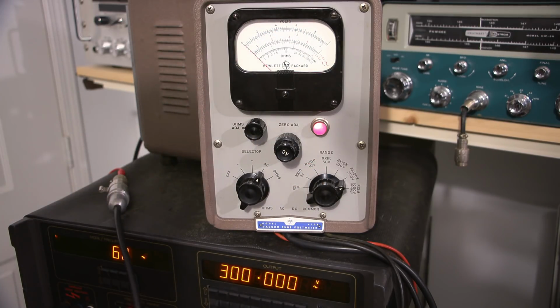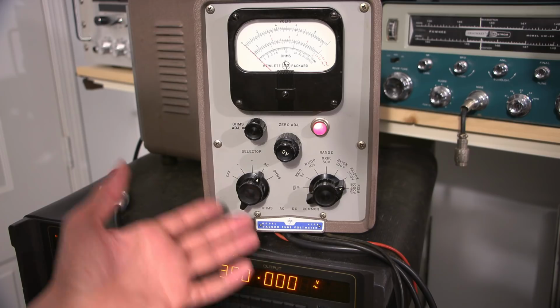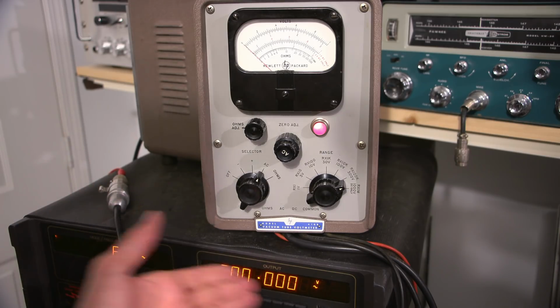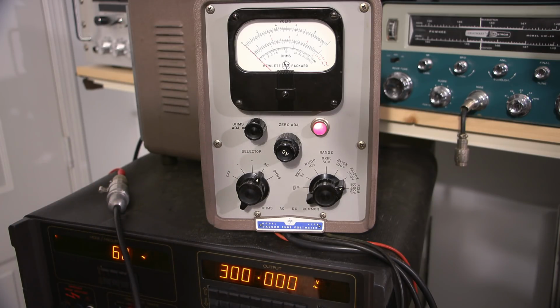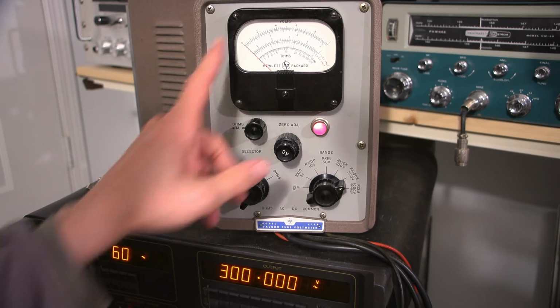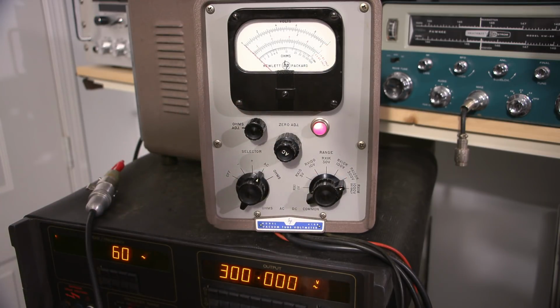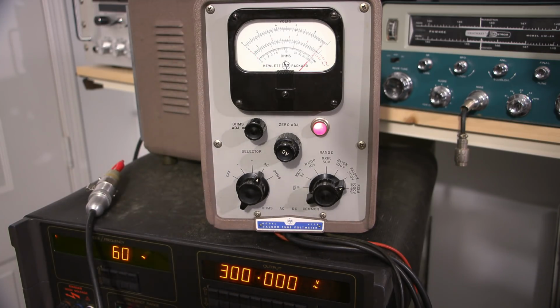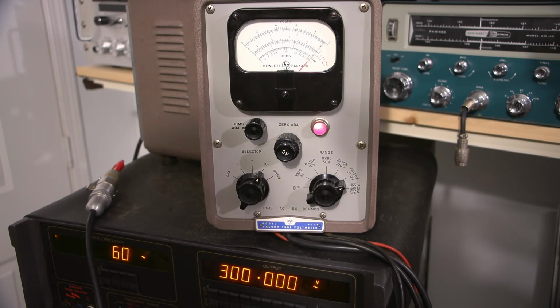I'm over on the 300 volt scale now, and the thing just aligns up so incredibly nice. So I'll give you an example here. So the calibration fixture is set to 300 volts. I'll turn that on. It's at 60 cycles, again, as you can see. You'll see it'll go right over to the 3 here. That noise is just warning you that it's putting out high voltage. Right on the number 3. So I'll turn that off.